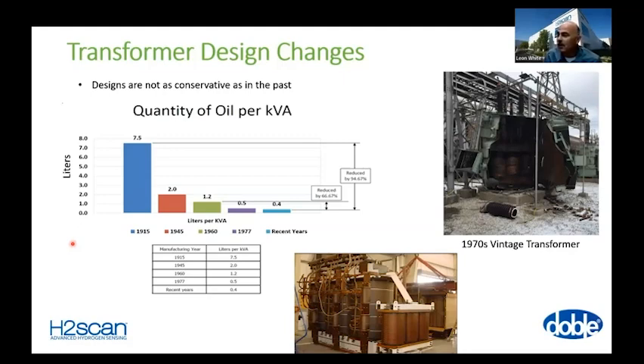in service? And so I happened to be working with a customer, probably 10, 12 years ago, that had a transformer failure at a power plant. The picture on the right is a transformer that was an auxiliary transformer at a power plant, and prior to its failure had no history of problems. The point of me putting it on this slide is this was a 1970s vintage transformer. You can see how small the windings were in that transformer for how big the tank is. And of course, today's designs you wouldn't have near that much space.